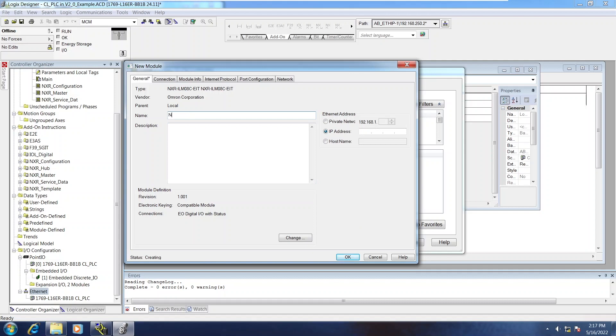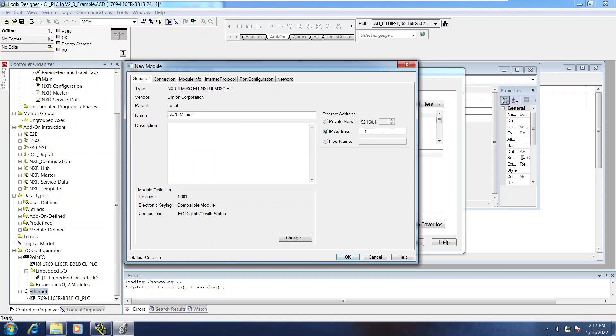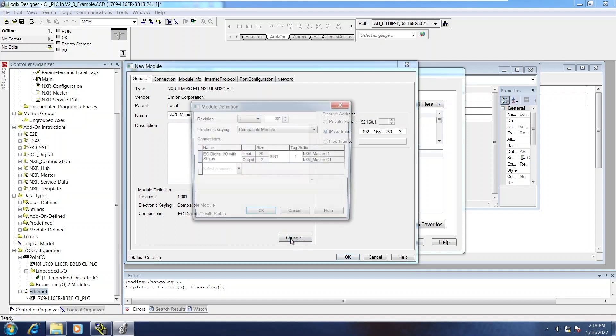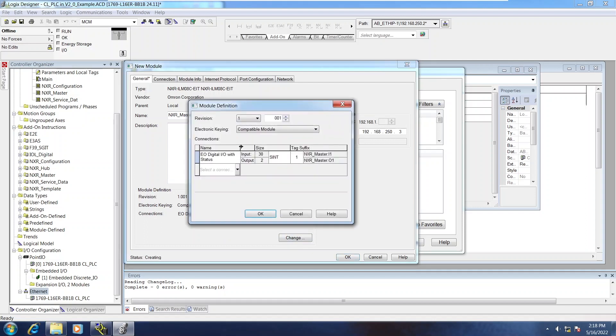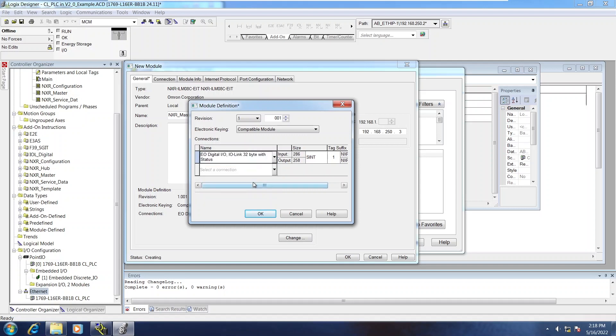The IP address that the NXR is currently at is 250.3. And the default module definition needs to be changed. That will be changed to exclusive owner, 32 byte with status, and the data type will be an integer.